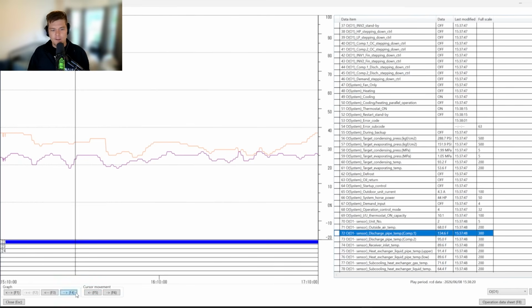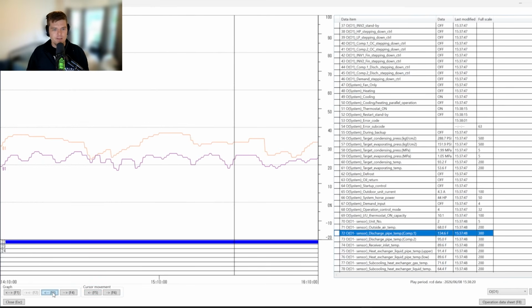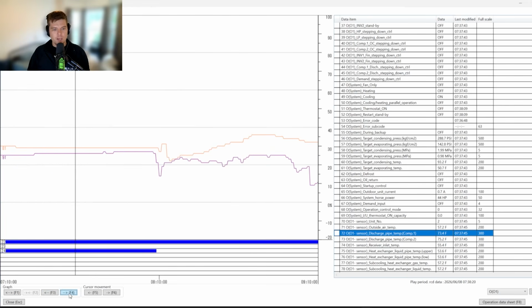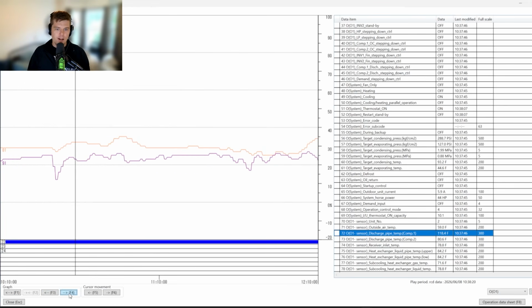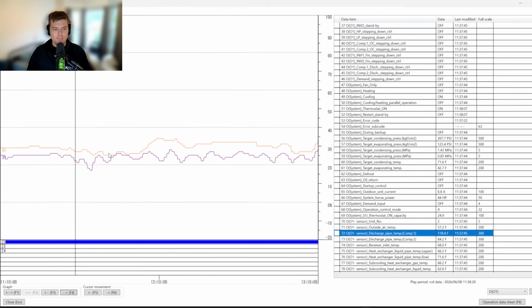And as you can see, that's all I wanted to say. Just VRT will get you sometimes if you're not looking for it. VRT will also mess with the operational data that you look at. Something like this, if it were to get to that modulation where it landed at zero suction superheat and stayed there and the demand was still on, I would go looking for the liquid, I'd go looking for the overcharge. But for this, the demand is just so low.